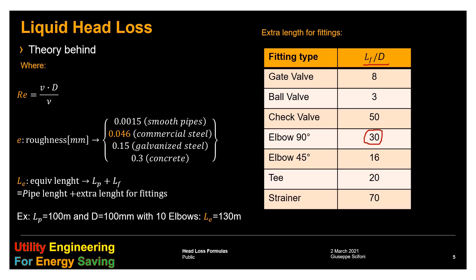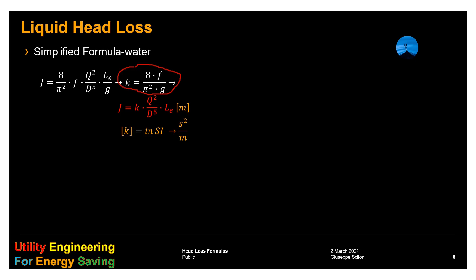Let's work out the formula by replacing V, the velocity, with the flow rate Q divided by the area, pi d square over 4. And we use the equivalent length LE instead. Then we define the constant K as per this expression. And we come to the pressure drop function of Q square, inverse of diameter to fifth and proportional to the length. Actually, K is not a constant, it depends upon F. But if we consider only turbulent flow, which is generally valid for water, F is only depending upon material and pipe size.